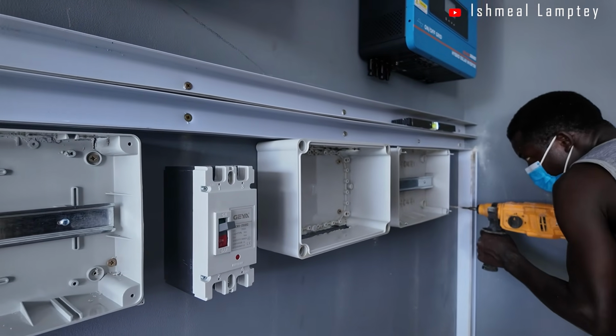For the AC input, it was single phase, so that was an additional 2 cables for one inverter and 2 for the other, making 8 plus 4, a total of 12 cables. You also have to include the earth cable as part of it - we always try our best to include that in all installations, because that's the right process.